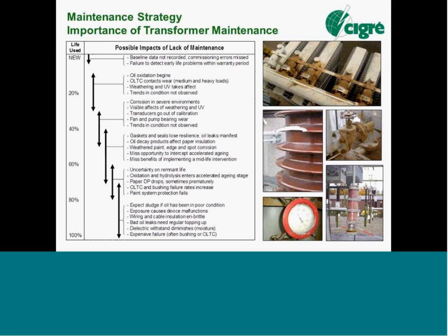Ross, question from Scott Lexon in the chat window. He's asking, to what extent should these recommendations be applied to transformers less than 69 kV or 25 MVA? Say that the most common condition monitoring done on a power transformer or any transformer would be oil testing, especially dissolved gas analysis. So you'd do oil sampling and testing on nearly every transformer if you're concerned about knowing its true condition, whether any incipient fault is at play, active gassing inside the transformer.